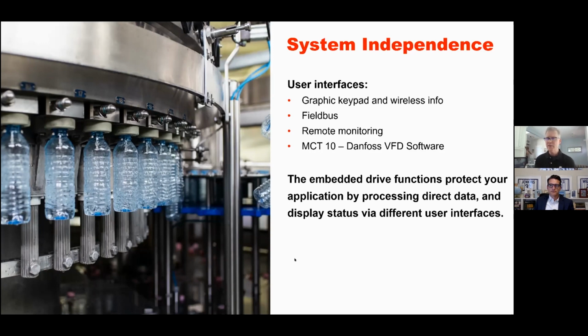So on the HVAC side, it's really pretty unique because you can take all this information and go over that type of building management system, as well as the industrial side where you're looking at the Ethernets and the Profinets, Profibuses, and things like that. And last but not least, the Danfoss VFD programming software, the MCT10. That is 2 versions. One's a free version, which covers 99% of applications. But since this is an advanced software, there's an extremely low-cost software, the MCT10 Advanced. And that's what we use to program it. That's what we use to monitor it.